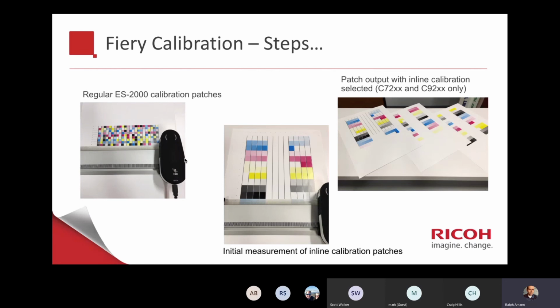The concept is like this: when you select an inline calibration, even for the first time, you create a new set. It wants you to use the spectrophotometer one time, as we're doing here in the middle, to do those readings. After that, it has a data set and it can use the inline calibration for recalibration. Keep in mind, the inline sensor is not a spectrophotometer, but more like a sensor, a bit more basic. But that's the workflow, and you can recalibrate ongoing with that.